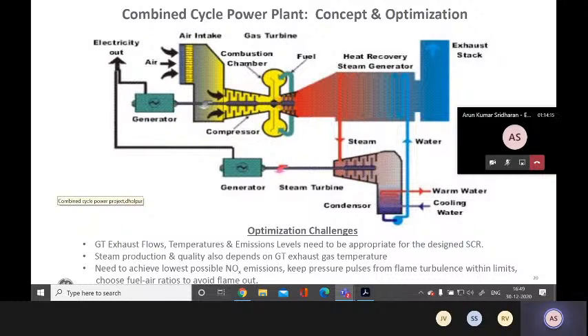So GE has developed a software suite where the user, the control room engineer, will basically put in his goals. And the software will rely on a number of digital twin models. It'll take in a lot of inputs regarding the plant conditions, and also some financial information regarding the cost of fuel and things like that, and some of the other constraints, and basically provide a startup path for the control room engineer, so that he can, in the most optimum way, take the power plant from zero load to the maximum load to achieve his objectives.